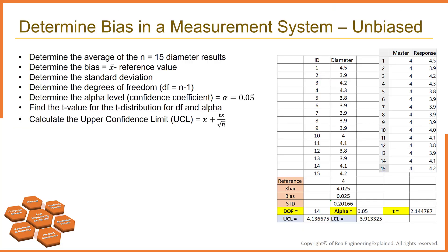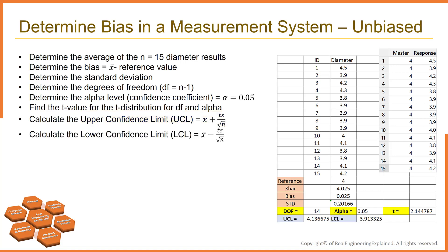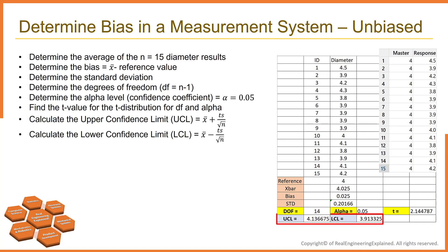Then calculate the upper and lower confidence limits. The upper confidence limit equals x-bar plus the t-value multiplied by the standard deviation divided by the square root of n. The lower confidence limit equals x-bar minus the t-value multiplied by the standard deviation divided by the square root of n. Since the confidence interval contains the reference value of 4 millimeters, the engineer concludes that there is no evidence of bias.